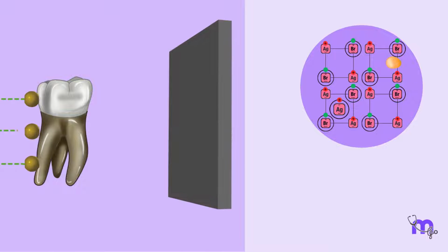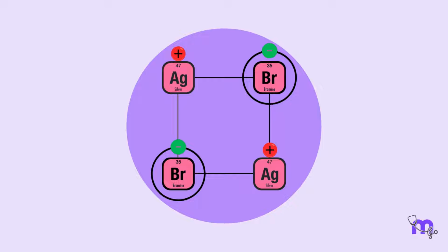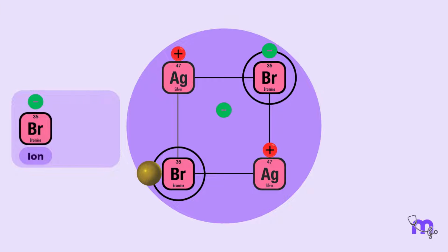When a beam of photons exits an object and exposes an X-ray film, it chemically changes the silver halide crystals to finally constitute the latent image. Let us see how this happens. After exiting from the object, when the photon reaches the film, it interacts with the negatively charged bromide ion. An electron is released, thereby converting bromide ions to bromine atoms.